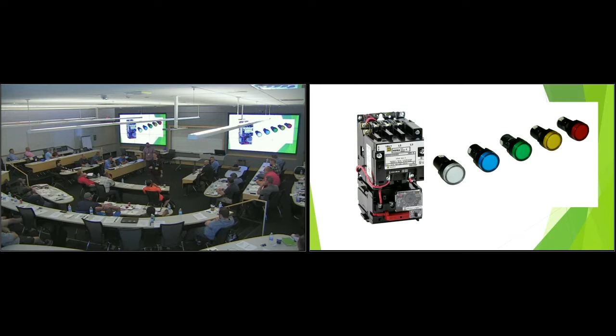The motor overloads are typically going to open if you get some kind of locked rotor issue or the motor starts to draw too much current. This goes back to saving money. If that $10,000 motor is overloaded, or the bearings go bad, or it's starting to single phase, we want to protect that motor and protect our investment. So the overloads accomplish that, and once we get beyond 1 horsepower, they're mandated by the NEC, and they're sized according to the nameplate, which we'll get into later.